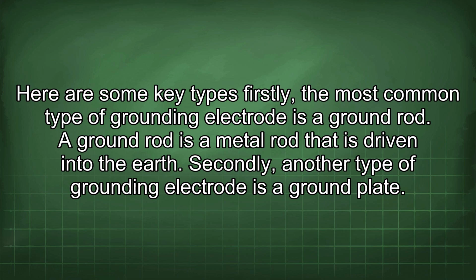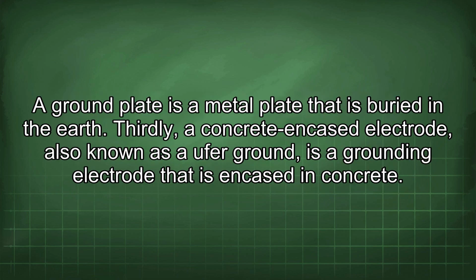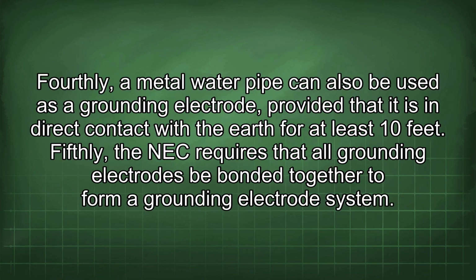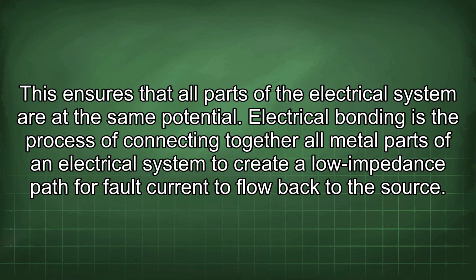Secondly, another type of grounding electrode is a ground plate. A ground plate is a metal plate that is buried in the earth. Thirdly, a concrete encased electrode, also known as a UFER ground, is a grounding electrode that is encased in concrete. Fourthly, a metal water pipe can also be used as a grounding electrode, provided that it is in direct contact with the earth for at least 10 feet. Fifthly, the NEC requires that all grounding electrodes be bonded together to form a grounding electrode system. This ensures that all parts of the electrical system are at the same potential.